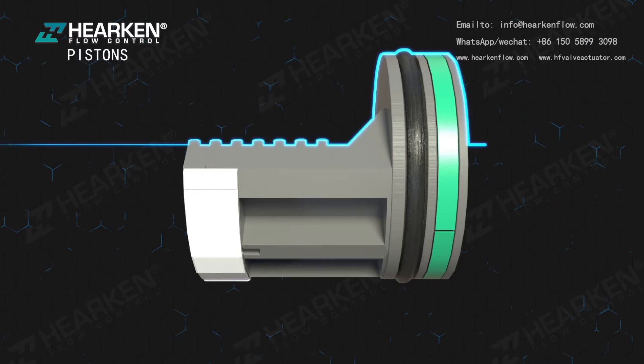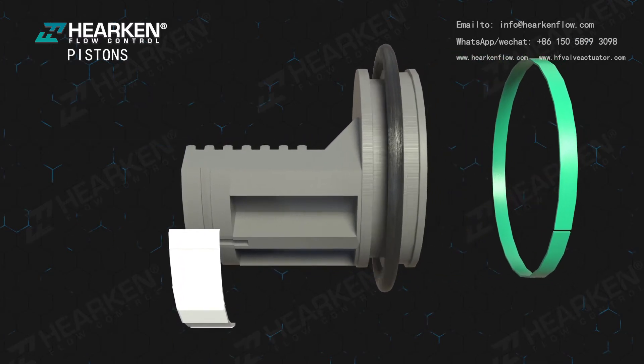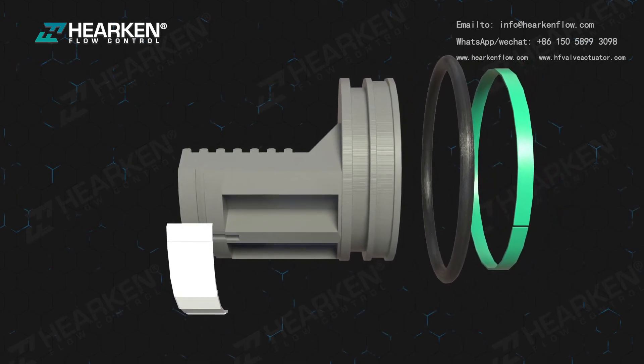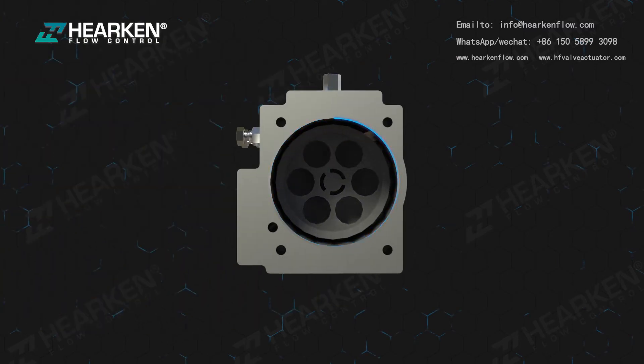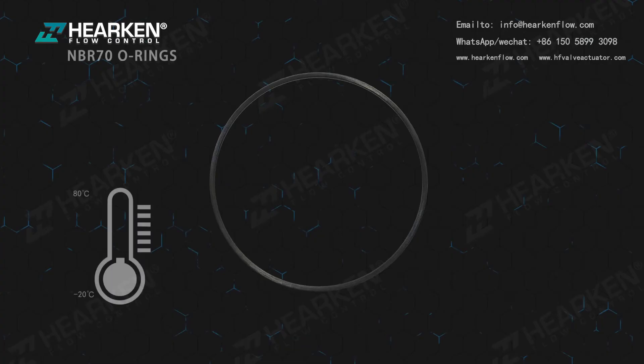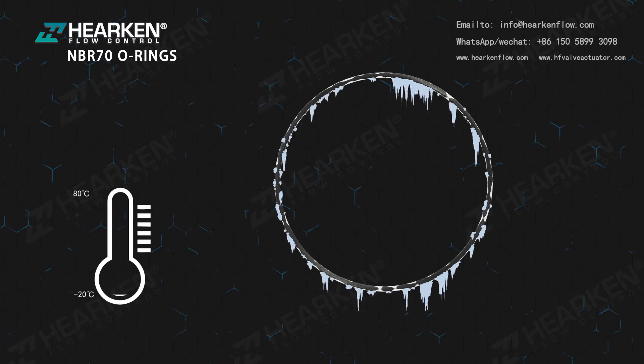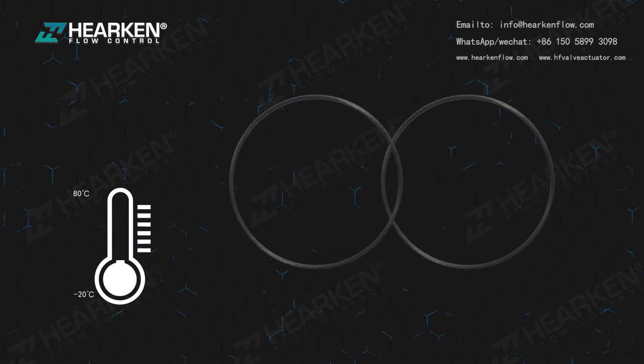The precisely balanced die cast aluminum pistons are fitted with high quality rings and guides, resulting in high ratios of output torque versus input air pressure. The twin rack and piston design creates a constant torque output on all models. NBR 70 O-rings are the regular standard, rated from -20°C (-4°F) to +80°C (+176°F). Additional seals are available upon request.